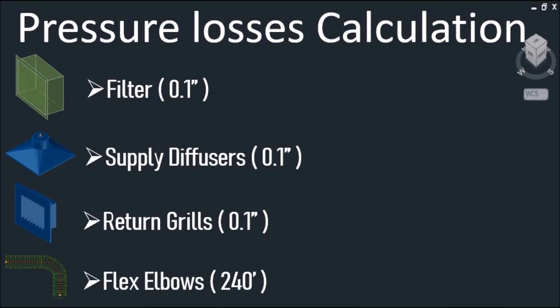It's very important to include components such as filters, diffusers, grills, flex elbows, and dampers. For this system design, the filter, supply diffuser, and return grills will each use 0.1 inch of water column. For our flex elbows, we are using 240 feet equivalent length of duct.